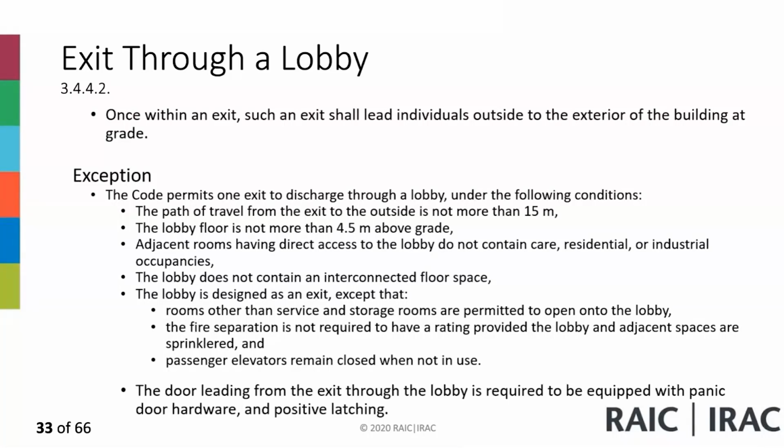So the lobby floor is a height limitation. You don't want the floor of the lobby to be more than 4.5 meters above grade. The path of travel through the lobby to the outdoors is not more than 15 meters. So once you get from your stair into the lobby, from your stair door to the outdoors should not be more than 15 meters.